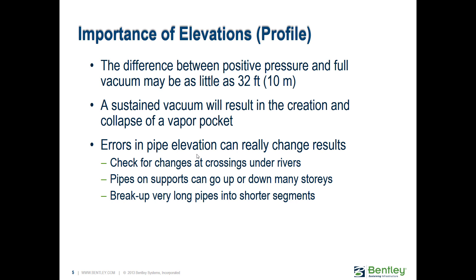When it comes to elevations and profile, the difference between positive pressure and a full vacuum is basically 10 meters. The vapor pressure limit at most elevations is 10 meters below zero. A sustained vacuum will result in the creation and collapse of vapor pockets. Any high points with potential for vapor pockets to form are very important to consider, and errors in pipe elevations can significantly impact the transient response.